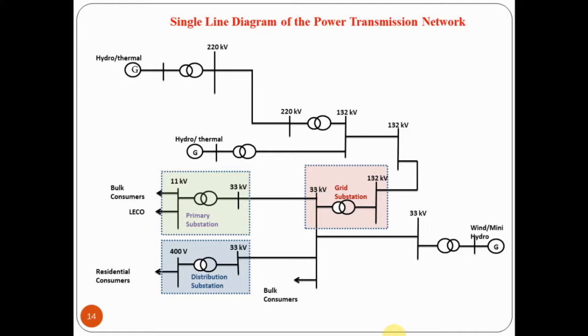But when this is not available, they should be able to bring power from this end also. Previously, protection and all the operations were set up for power coming from this side only, but now you should be able to handle power coming from this transformer or from this mini hydro. Also, if there is excess power from this side, for example if there is heavy rain after midnight, there may be no demand here, so this power will have to be transferred through this. So the protection equipment here has to be able to cater to this also.